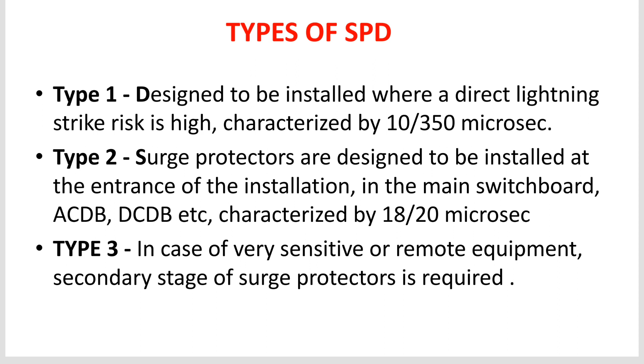Type 2 SPD is the main protection system for all low voltage electrical installations. Mainly all these switchboards, these sub distribution boxes, ACDB, DCDB, all of these contain Type 2 SPD. Type 2 SPD is characterized by an 8 by 20 microsecond current wave. Type 3 SPDs have low discharge capacity, and these are used where your equipment is very sensitive, and these are used with your sensitive or remote equipment.